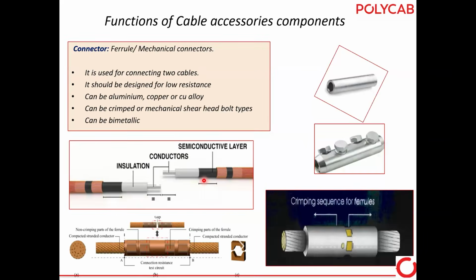For electrical connections, we use the ferrules or the mechanical connector. It is used for connecting 2 cables. I have shown the pictures here. Jointers always prepare the cables as per the dimensions mentioned in the installation manual. They prepare first the conductor, then the XLP insulation. From here to here, remove the semiconducting layer. That way, the jointer prepares the cable as per the installation manual given in the box, and the cable has to be prepared as per the installation manuals only.